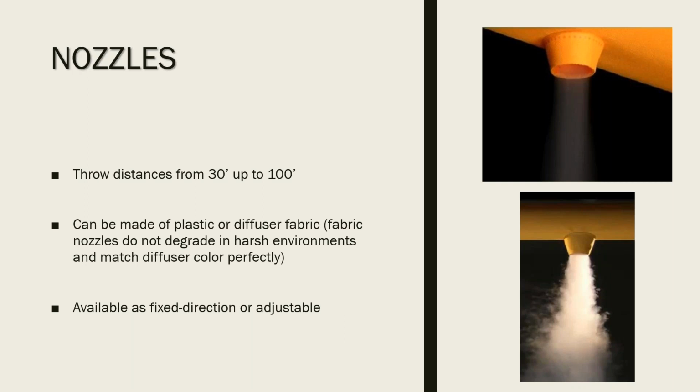I've seen these done instead of putting an end cap at the end of a fabric diffuser. I've seen owners wanting to throw air from the end of the duct, and so instead of placing an end cap, they just put this huge nozzle, almost the diameter of the duct, to throw air across the room. So these can, again, be made in any size.